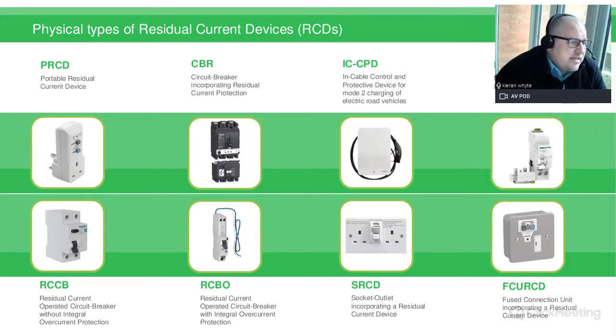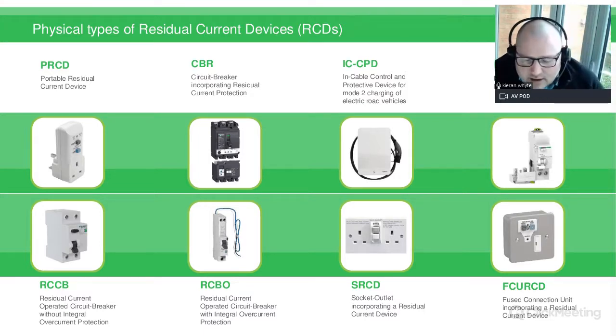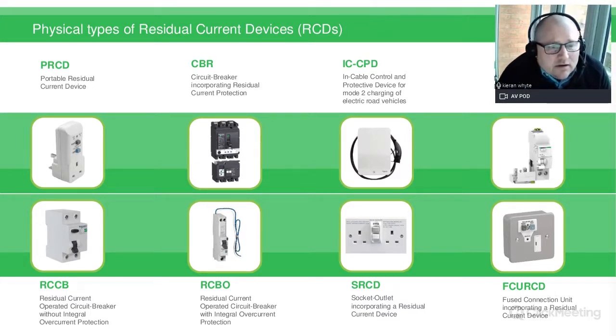If you go below that, we have the RCCB, which is more commonly seen in consumer units these days. Back on the top line, we've got the CBR, circuit breaker incorporating residual current protection. So that's over 100 amps kind of rating, and it's an add-on module. And then below that, we have the RCBO, which of course is an MCB, which gives you overload protection and short circuit, and with the addition of earth leakage combined together in one unit. Back on the top row there, we have the IC-CPD, in-cable control and protective device for mode 2 charging of electric road vehicles. Obviously, EV charging is a massive growth industry in our industry at the moment, but again with that increased danger, because we've got electricity outside of what used to be called the equipotential zone, we need to make sure there's enhanced safety there with the RCD.